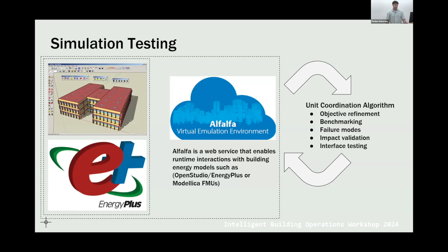The reason they're able to use the EnergyPlus model is because they have a wrapper that goes around EnergyPlus called Alfalfa that allows you to step forward. Usually when you run an EnergyPlus model, you get aggregate data that spits out all at once. You might have the time series data, but you're not able to implement any changes along the way, so you only get the final outcome. The Alfalfa model basically allows you to step forward in minute increments, so you can make changes to the set points the way you would with a thermostat.